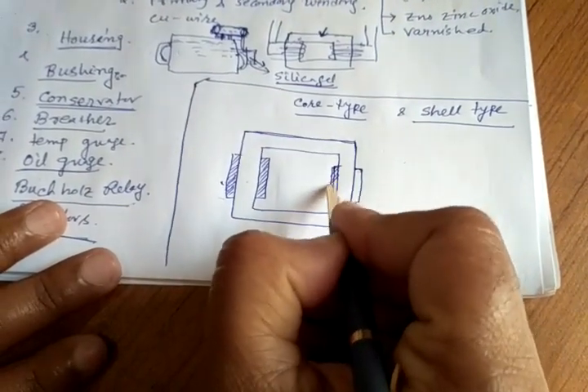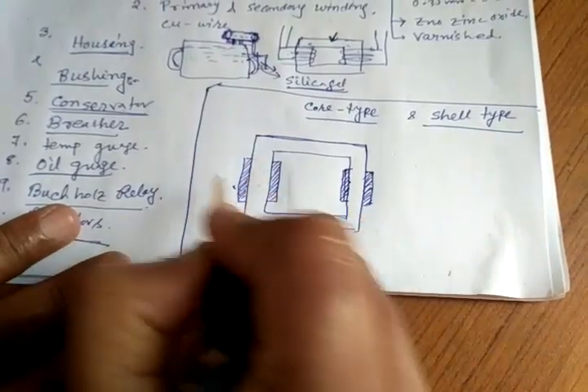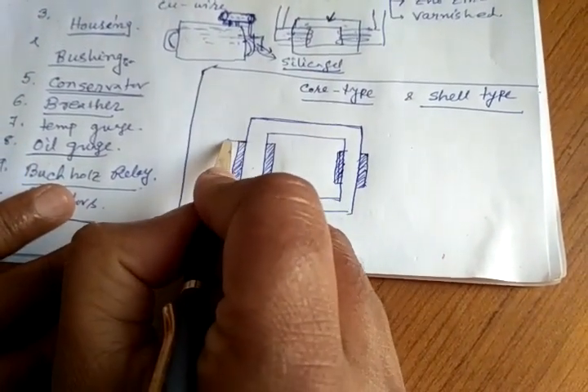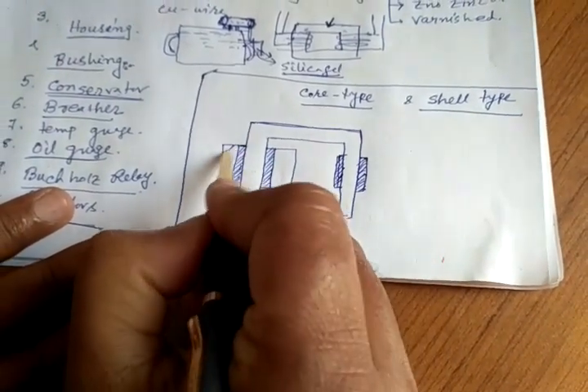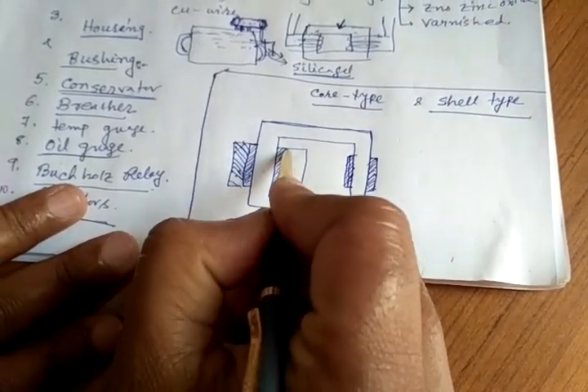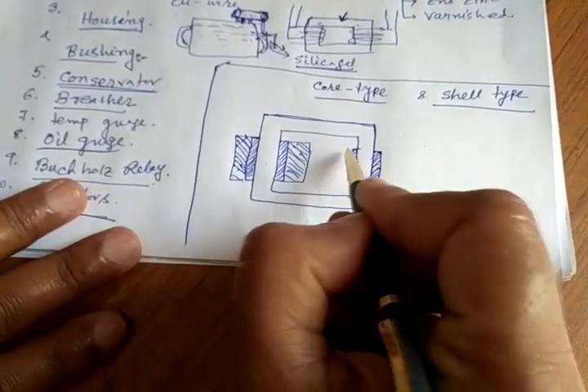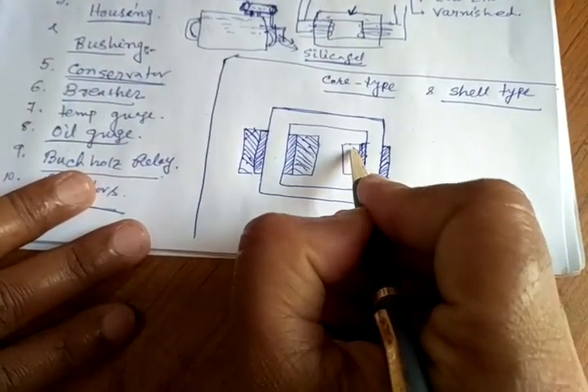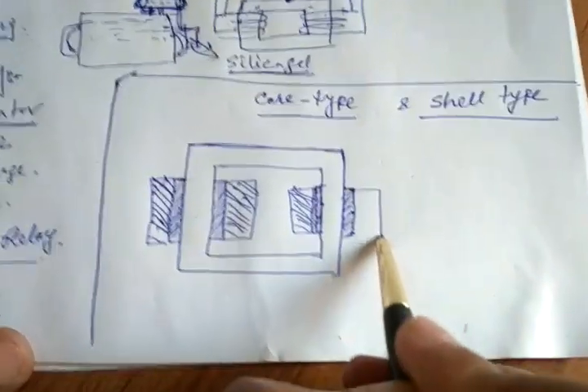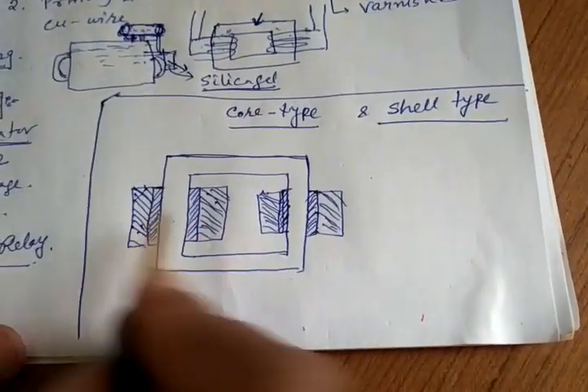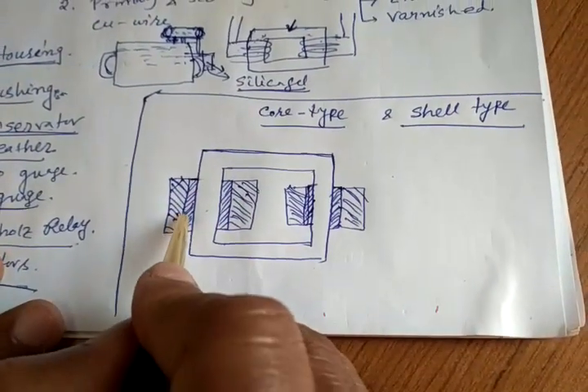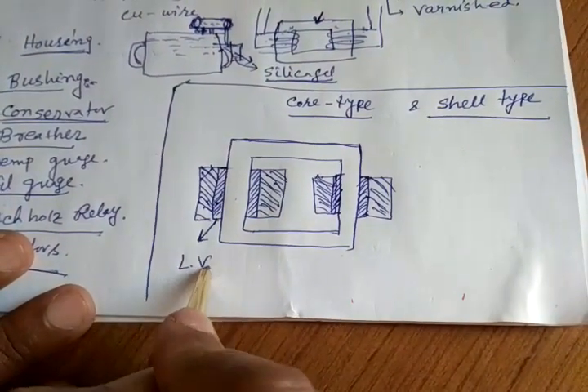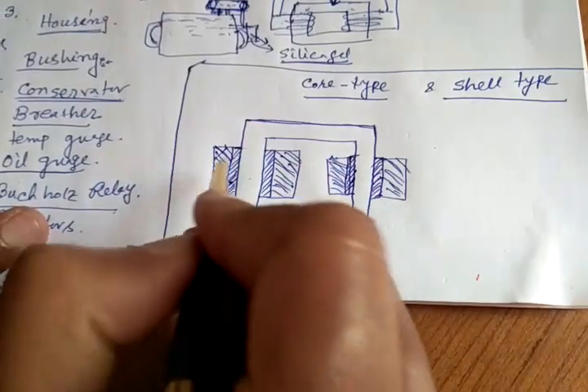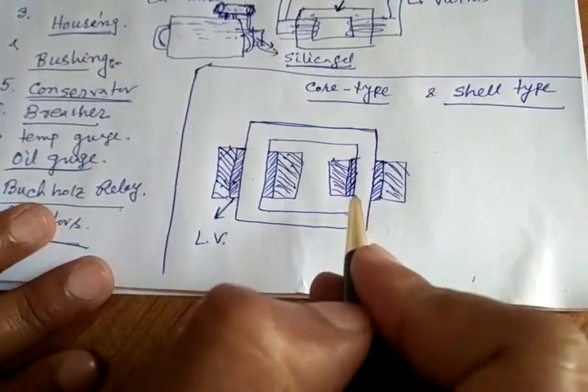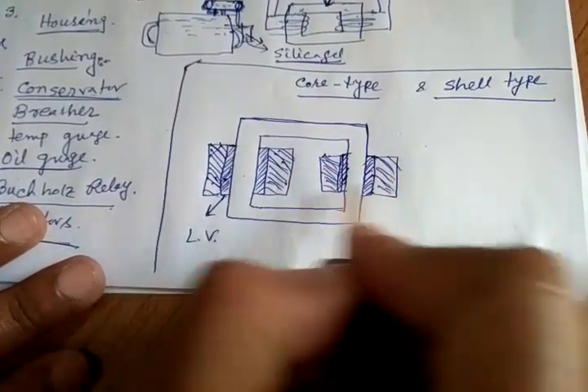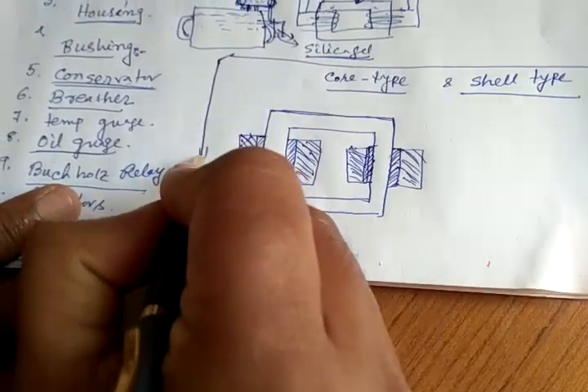Here also helps. First we give some turns of low voltage winding, then on top of it we give the high voltage winding, this way. This has certain advantages, and this is the high voltage winding. So both the limbs contain primary as well as secondary. This is the low voltage. Generally, low voltage winding is given inside, and on the outside, first low voltage winding is given half here and then half on this limb. Then on top of it, high voltage winding is done half here and then half here. So this outside one is the high voltage one.